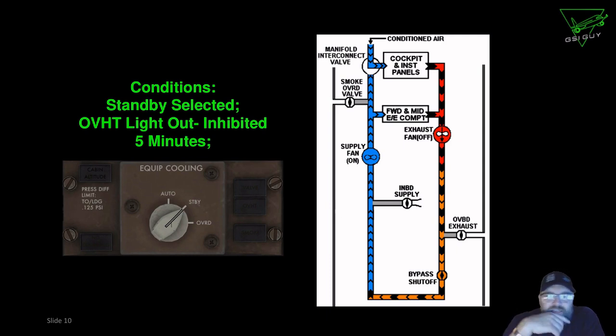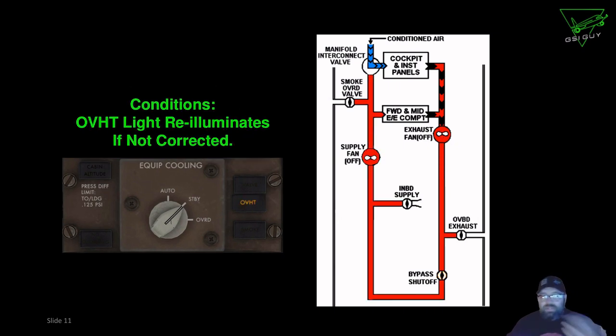Now, if you notice over here, it says condition standby selected, overheat lights inhibited for 5 minutes. Okay, so the overheat light extinguishes whenever we go to the standby position, regardless of whether or not the overheat condition is gone or not. Because what it's doing, it's giving the system a chance to change and to operate correctly. That's really what it's doing. So it gives it 5 minutes, and then after the 5 minutes, it tests itself and it says, okay, is it still warm? Yep, it's still warm. Oh, crap. And then it puts the overheat light back on there. If it's not warm anymore, then the overheat light stays extinguished and you can continue operating in the standby mode. But, like I said, if it's not corrected, the overheat light comes back on after 5 minutes.